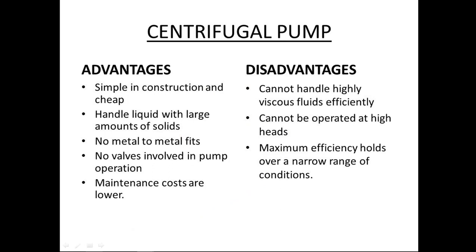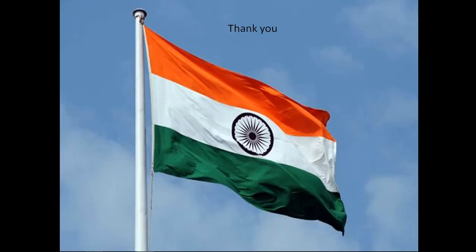And there are also some disadvantages of the centrifugal pump. The centrifugal pump cannot handle highly viscous fluid efficiently. Second, it cannot be operated at high head, and third, maximum efficiency holds over a narrow range of conditions. This is all about the working, construction, advantages and disadvantages, and types of various pumps.